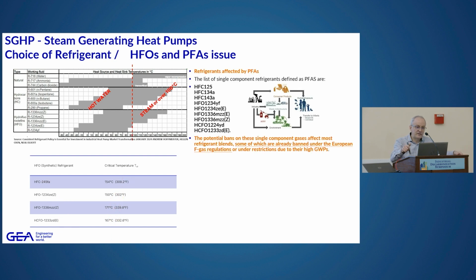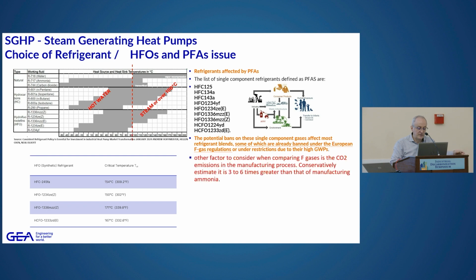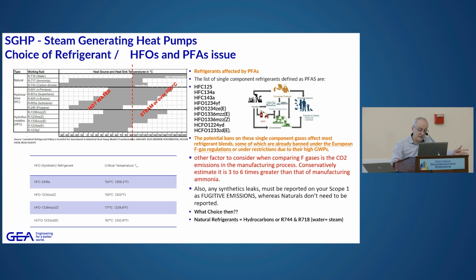The downside is that a lot of them are becoming a big problem in Europe, and now it's coming into the US, where some of them have become part of a watch list or radar list, as part of the PFAS and TFAS problems, these forever chemicals that are a danger to human health, animal health, and grounds. The other factor is that when you manufacture a refrigerant, sometimes it makes a lot of CO2 emissions. HFOs take about 3 to 6 times more CO2 emissions than making naturals. Also, you have to account in your scope 1 and scope 2 for the fugitive emissions. HFOs need to be reported. Naturals don't need to be reported. So what's the choice? If you need to make steam, go to hydrocarbons.